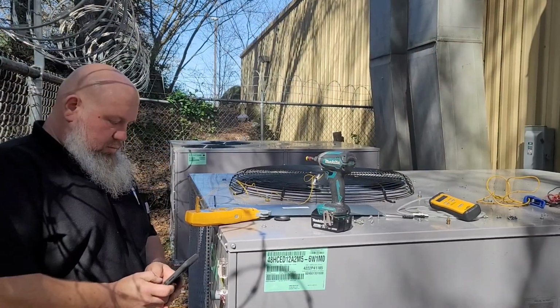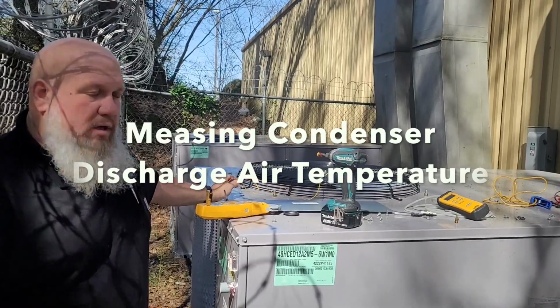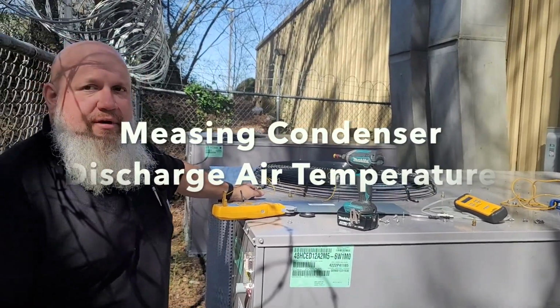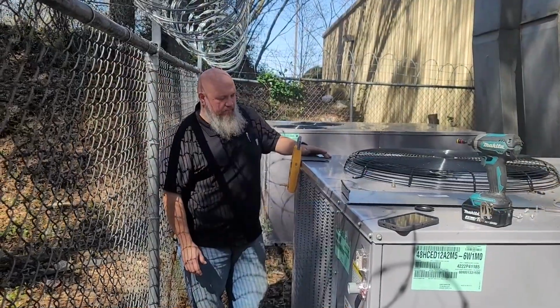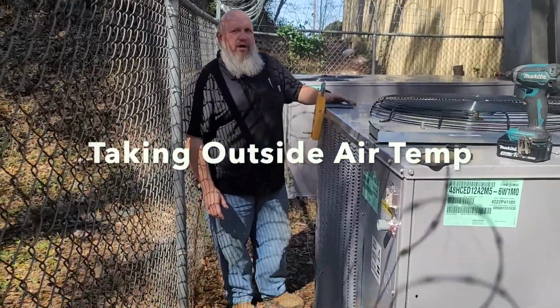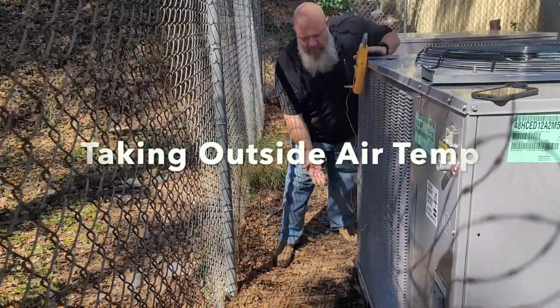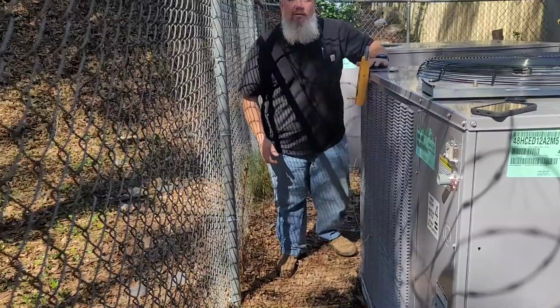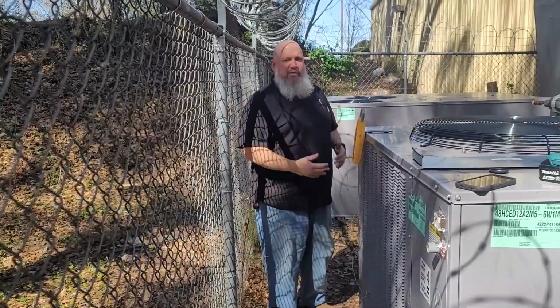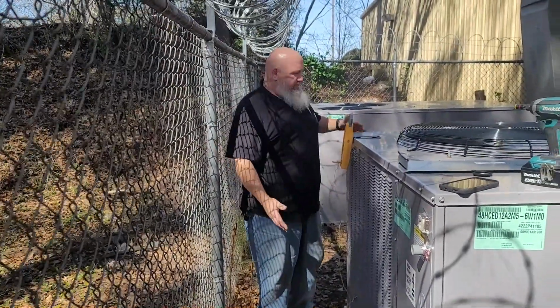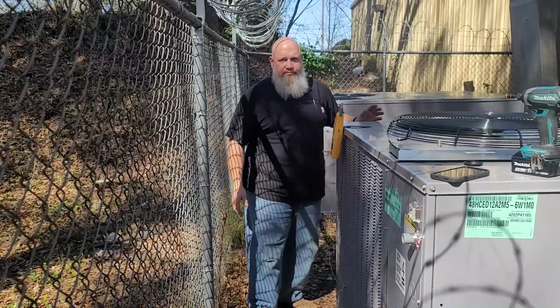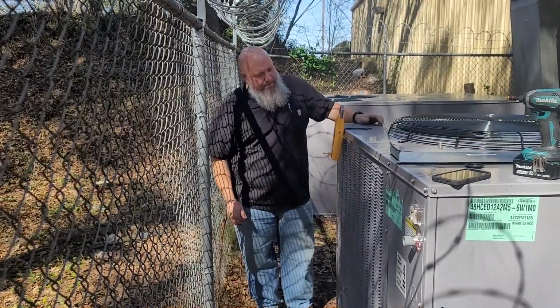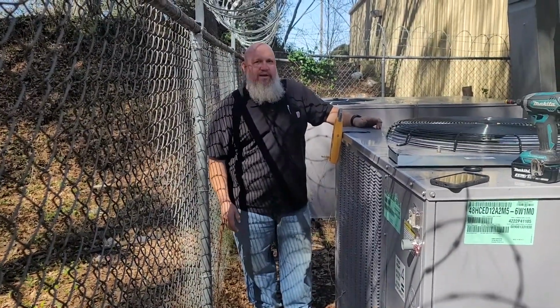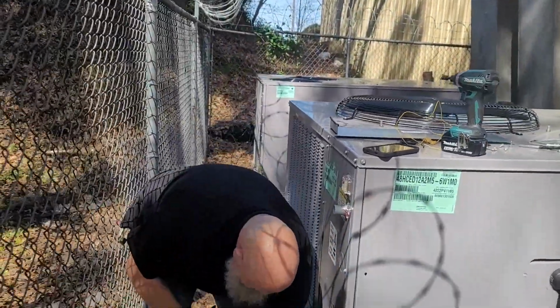Now on the DigiMEP form, you're taking what temperature now? The leaving air temperature of the condenser. So what are you doing right now, Mike? Checking the outside air temperature. Where are you taking that temp? About a third of the way up on the coil. It gives you a good, accurate temperature because that's where the air is coming through. So that's what the coil sees. Yes. Are you on the sunny or shady side of the unit? Shady side.